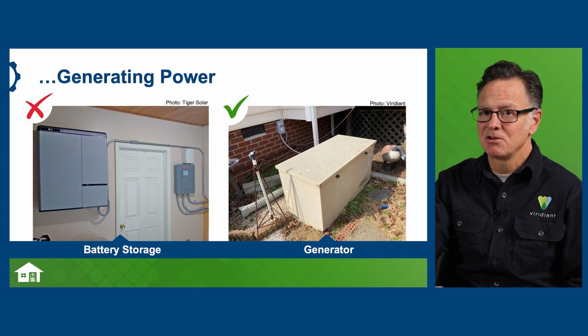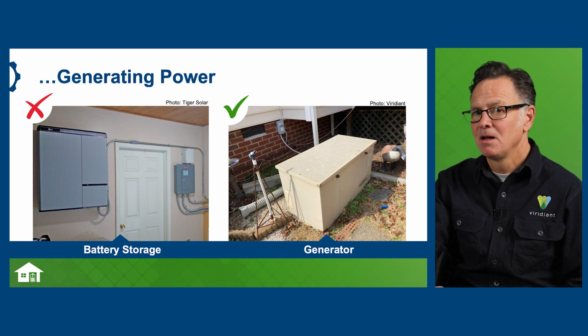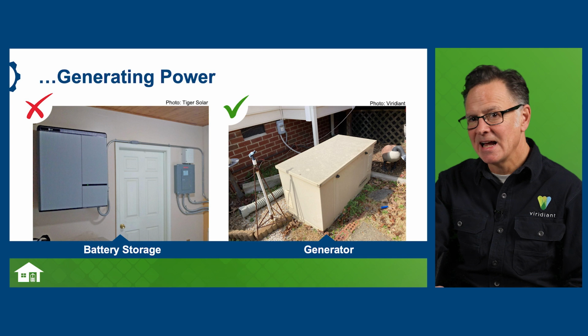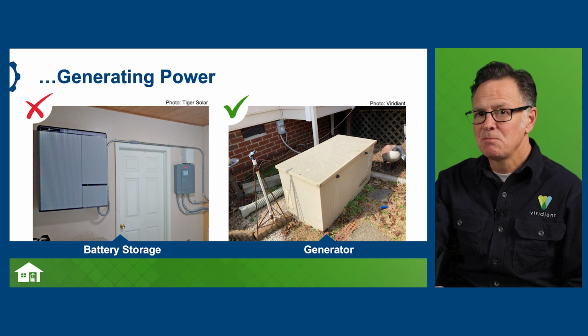Generators make electricity when they're running. As long as they have fuel, they will run and can power devices, but they have to stay running to have power available. A 22 kilowatt propane generator will use about 2 gallons per hour running at half load, 3.6 gallons per hour at full load.